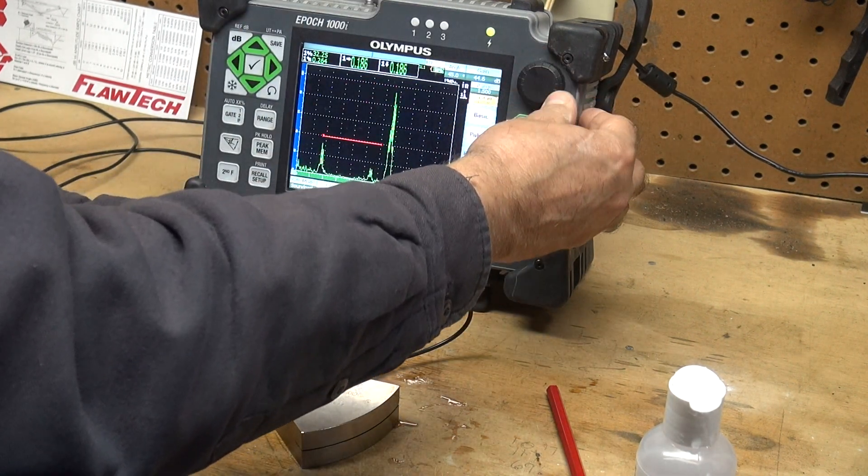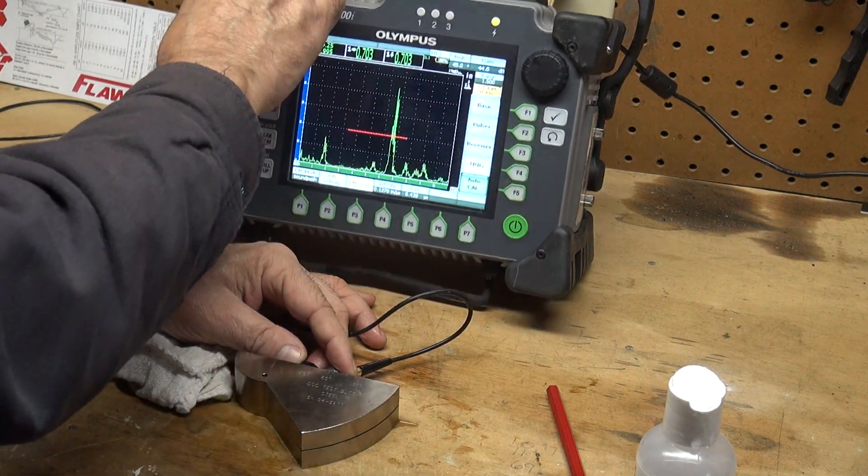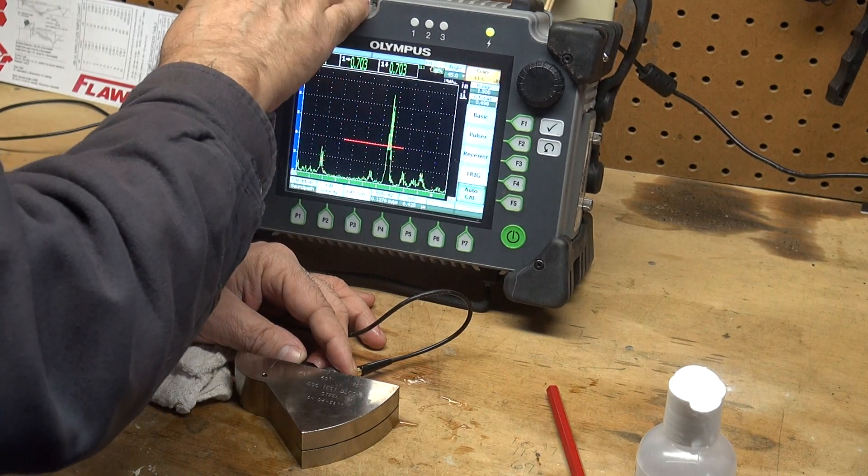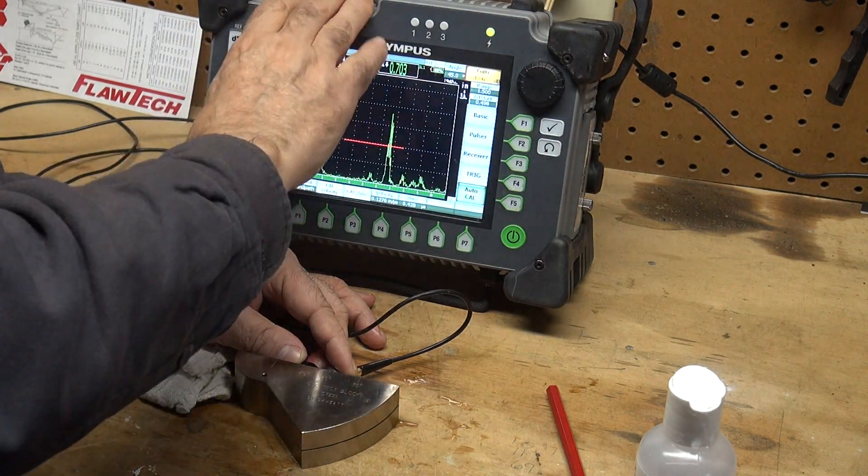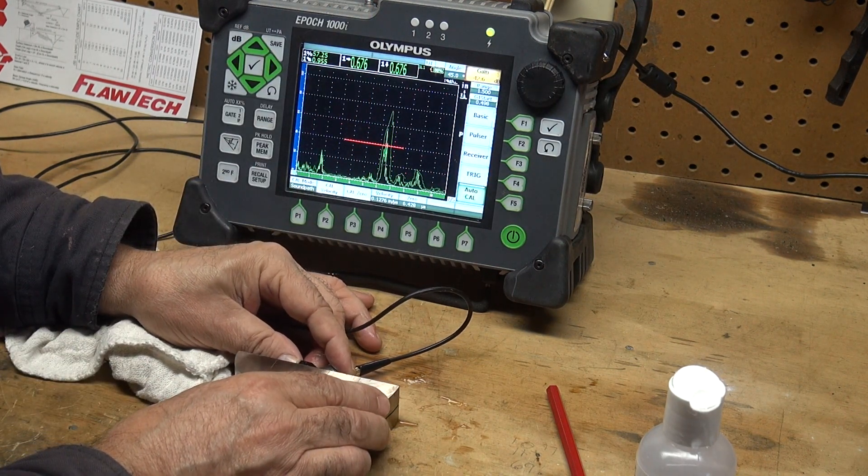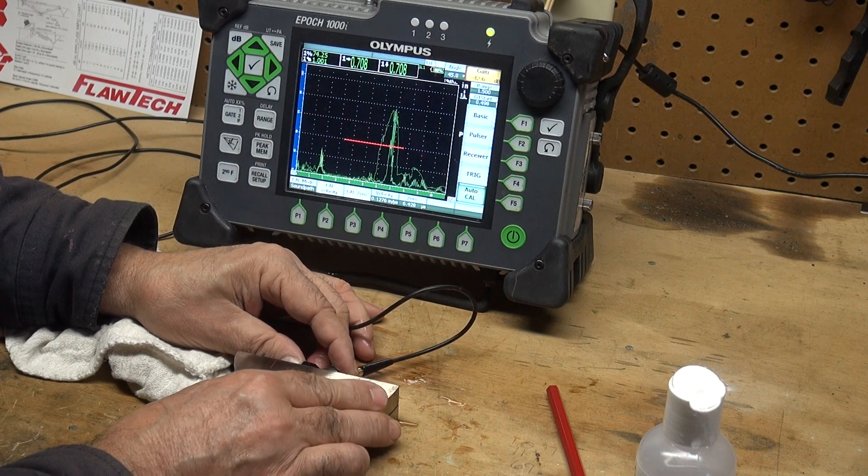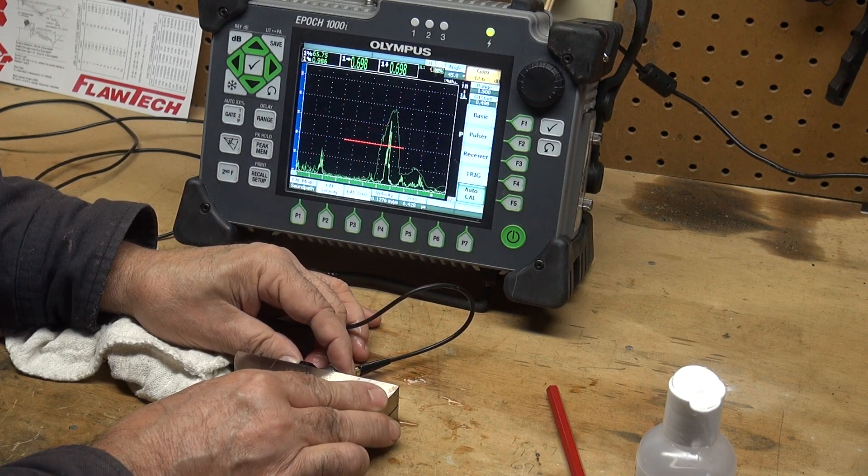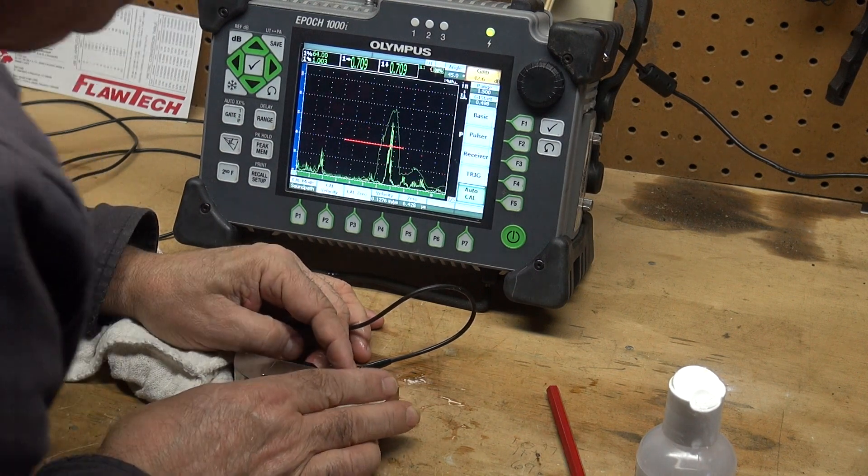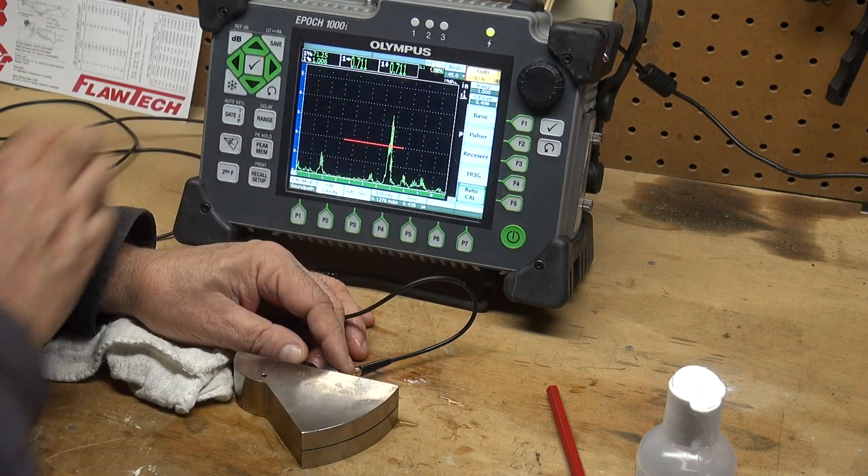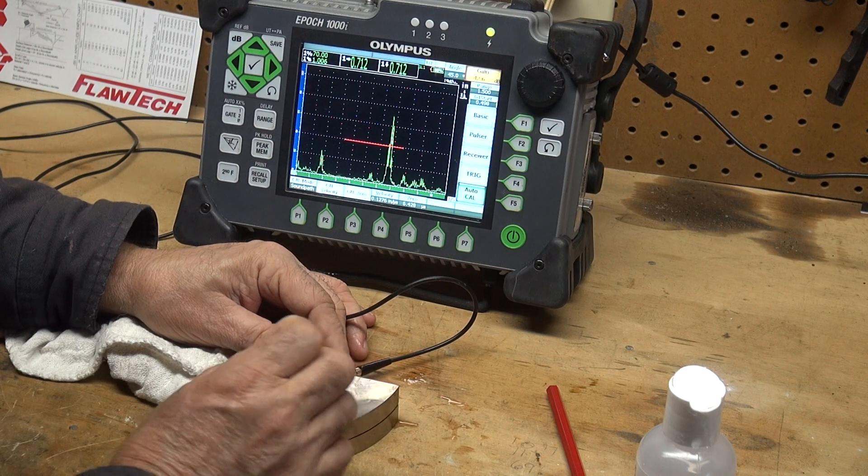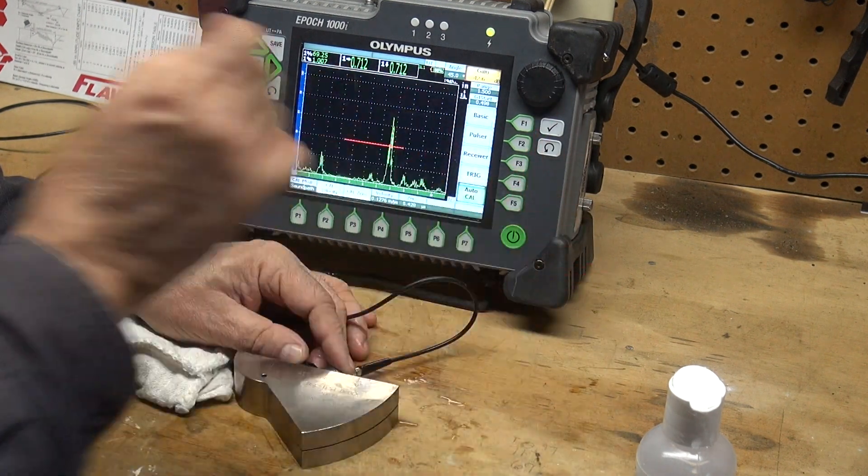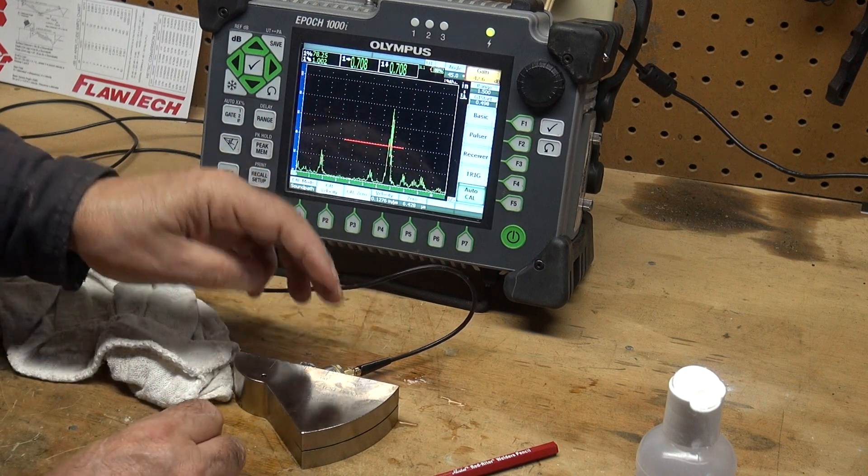And 45 degrees. So this hole right here, let me take the gain down a little bit, and let's hit the peak memory and I'll look at that, find the peak of that signal. Right about there is the peak of my signal. If I look at the 45 degree, it matches perfectly to my beam index point, so this wedge is a perfect 45 degree.